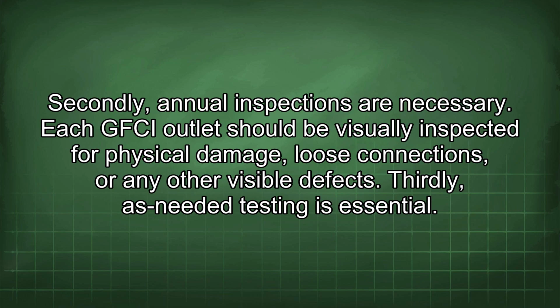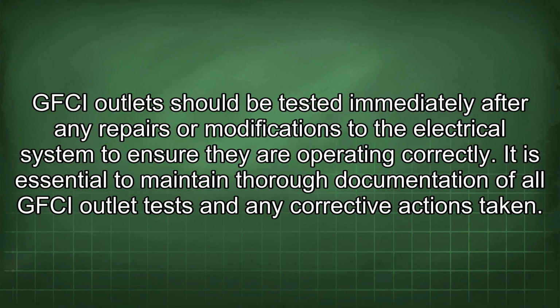Secondly, annual inspections are necessary. Each GFCI outlet should be visually inspected for physical damage, loose connections, or any other visible defects. Thirdly, as-needed testing is essential. GFCI outlets should be tested immediately after any repairs or modifications to the electrical system to ensure they are operating correctly. It is essential to maintain thorough documentation of all GFCI outlet tests and any corrective actions taken.